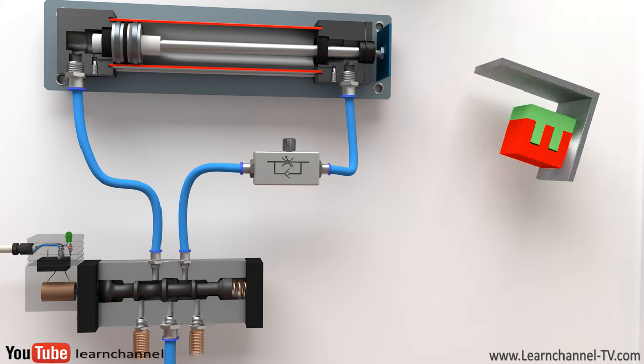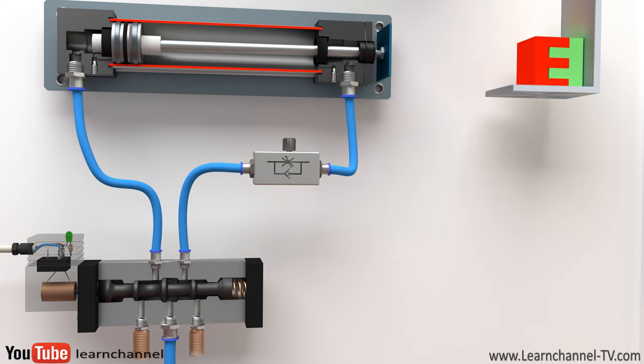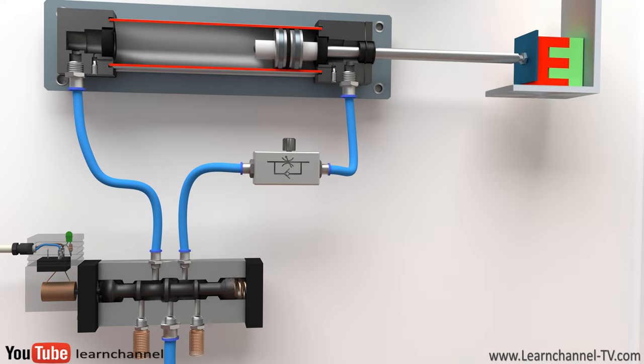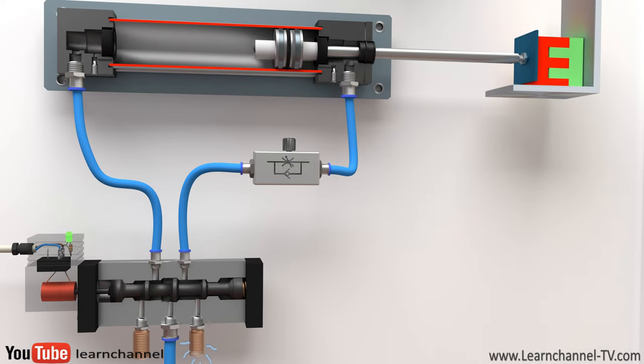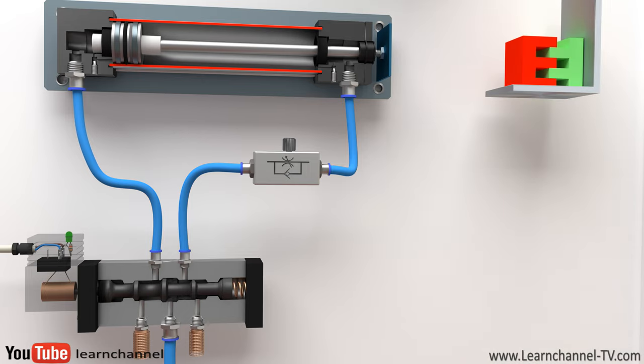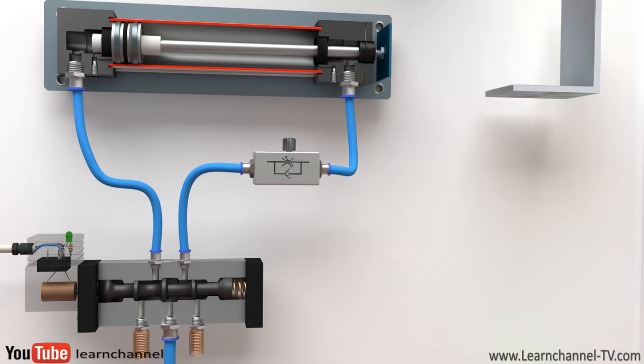Let's have insight of this valve. The moving part is commonly referred to as a spool. Here, the solenoid causes the spool to move within the housing against the spring force as soon as it is energized. As soon as the solenoid is no longer energized, the spool retracts to its initial position due to the spring force.